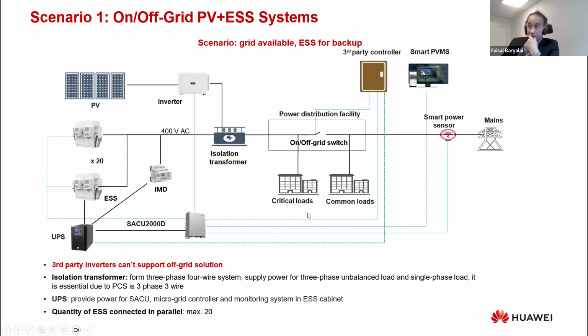Let's go through this picture again. The third-party controller will also be connected to SACU, to a smart logger, and to all other units. For instance, the meter, everything will be connected to the smart logger or SACU, and then everything will be controlled by the third-party controller in such a system. The power for the whole external unit, and also the units inside the battery which need an auxiliary supply, will be supplied by UPS. We have recommendations for what type of UPS and what capacity. We can show it later on.